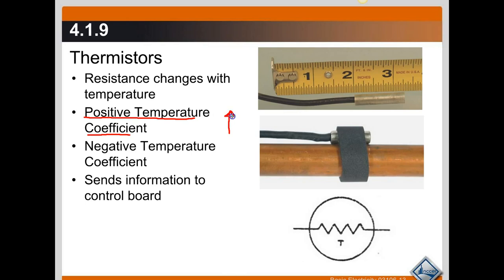Let's go over that again. Positive temperature coefficient thermistor: temperature rises, resistance rises. Negative temperature coefficient: temperature rises, resistance decreases. These are used exclusively to send information to a control board.